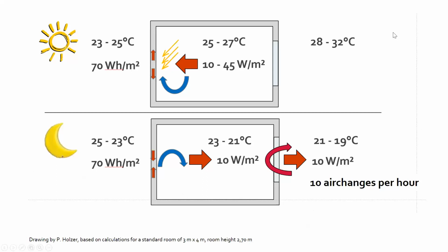First thing, if we... this should be a room. This is what a mechanical engineer thinks. It's a nice drawing of a room. If we go for night ventilation, first thing, we have to allow our indoor temperature to be a little bit higher than usually. So night ventilation with a constant cool room is nonsense, because the room has to get warmer to get it cool during the night.